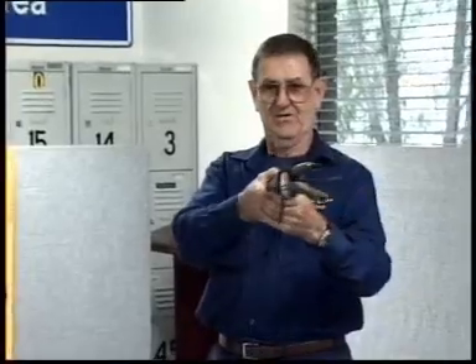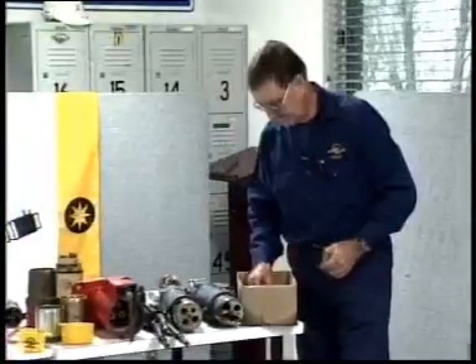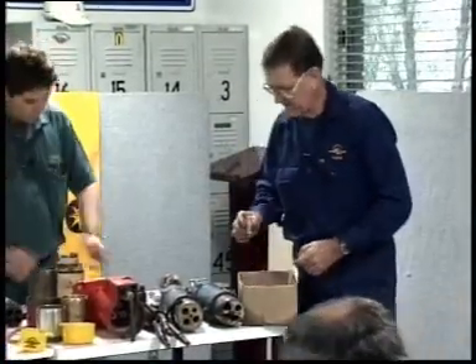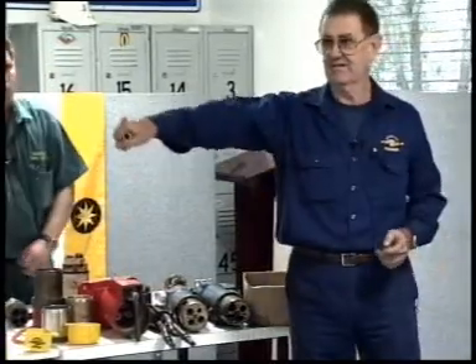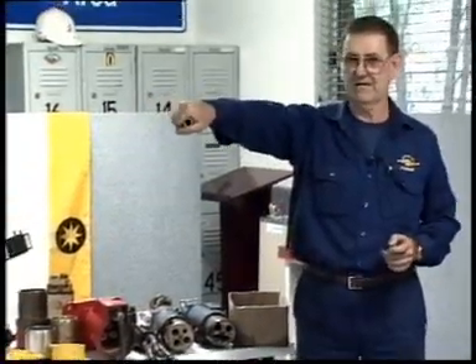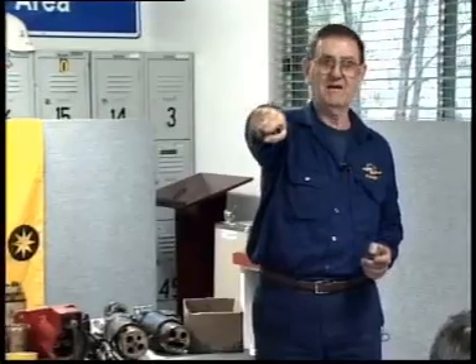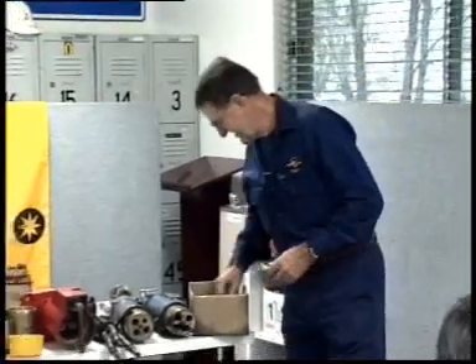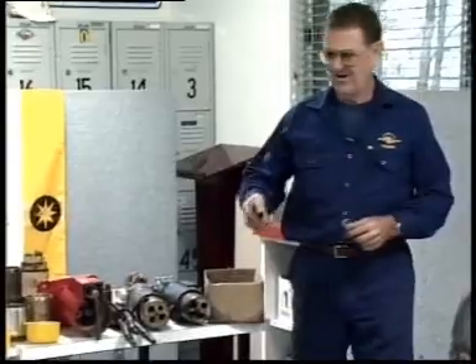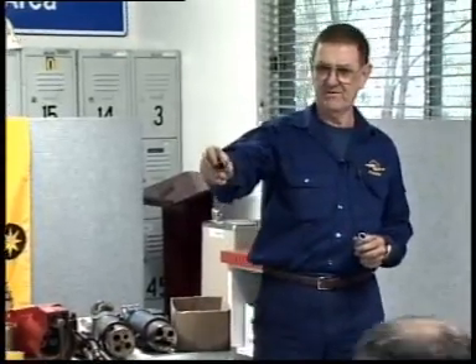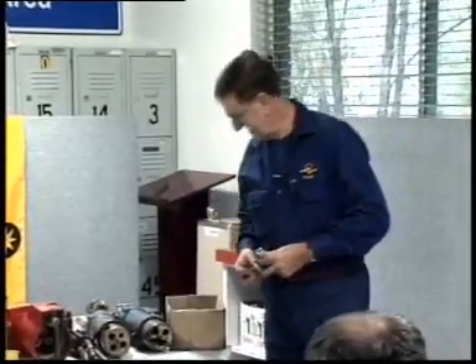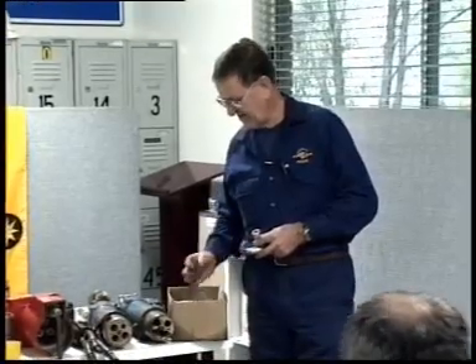You can see where all the contacts are burnt on the front end there, where it drew the flame out with it. With these contacts, when you look down the spout, all you're going to be looking at is something like that. That's all you're going to be able to see. Okay? Now, they don't have to be bright and shiny, but if you have a look at some of these that I've got here, you'll see where the front end of them is either damaged or badly burnt. You won't see that tinning on there. The tinning has disappeared because of the heat generated in there.